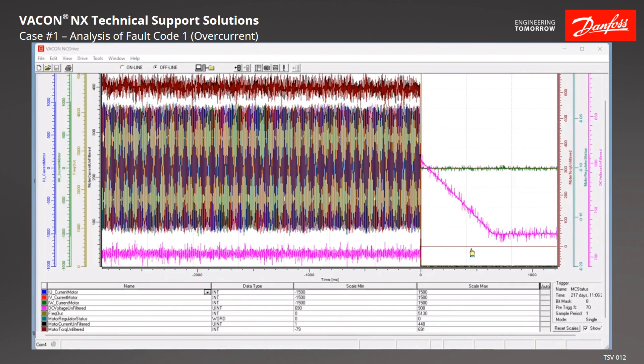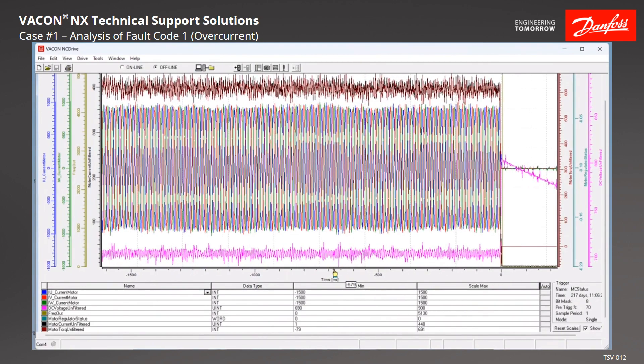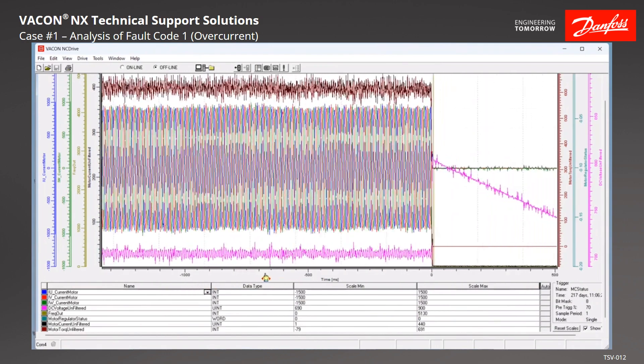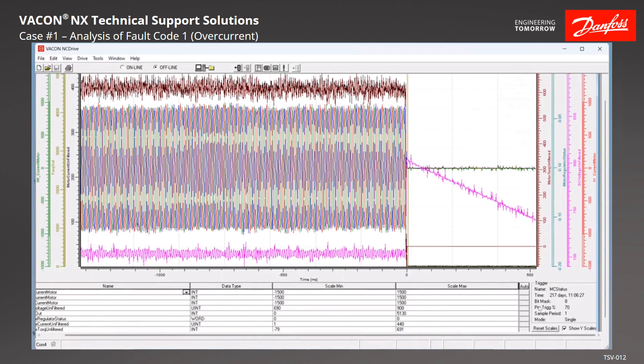This is the data logger for the service file we were looking at. When we open it, it looks like a bit of a mess — we need to manipulate the data to make it more readable. Using the bottom time bar, left-click pulls one way, right-click pulls another, and clicking both buttons lets you move it back and forth for finer adjustments. The zero spot shown here is where the trigger occurred, so that's generally where we want to start looking for our problem. The first thing we want to do is relate this logger to an actual fault using the timestamp: 217 days, 11 hours, 6 minutes, 27 seconds.